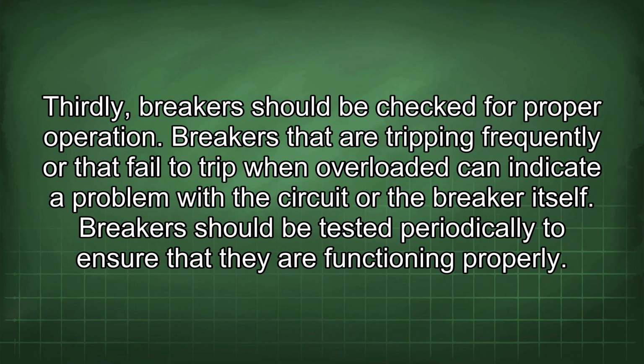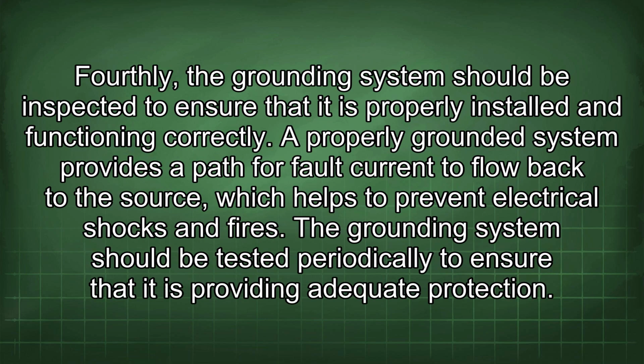Thirdly, breakers should be checked for proper operation. Breakers that are tripping frequently or that fail to trip when overloaded can indicate a problem with the circuit or the breaker itself. Breakers should be tested periodically to ensure that they are functioning properly. Fourthly, the grounding system should be inspected to ensure that it is properly installed and functioning correctly. A properly grounded system provides a path for fault current to flow back to the source, which helps to prevent electrical shocks and fires. The grounding system should be tested periodically to ensure that it is providing adequate protection.